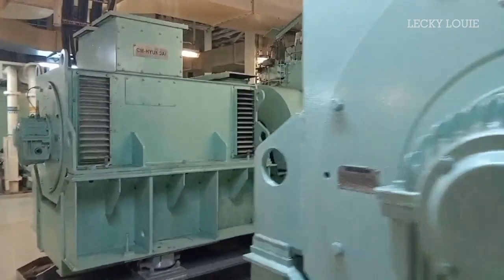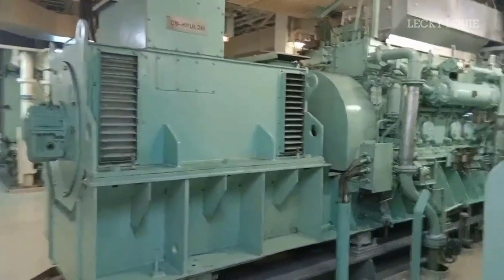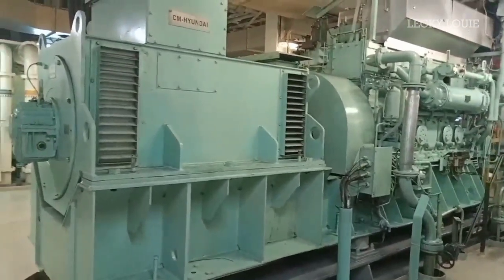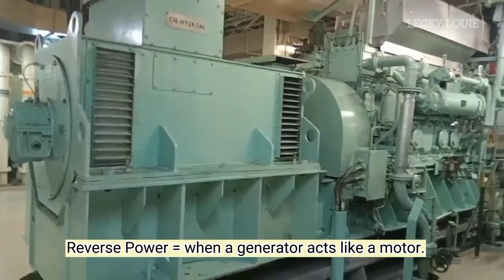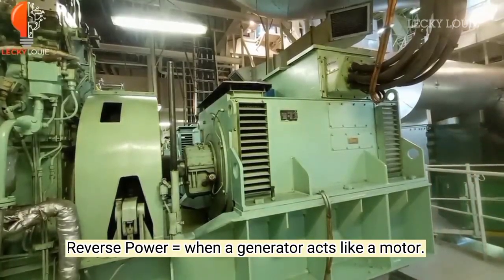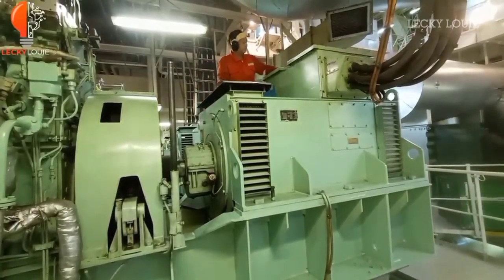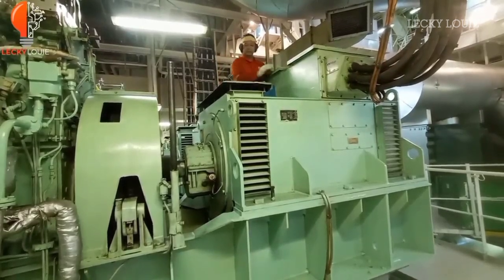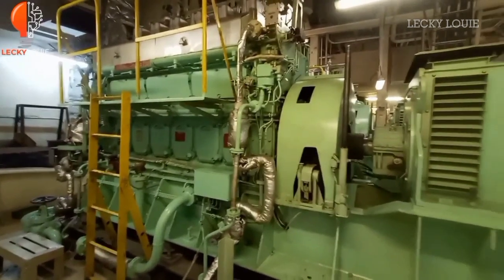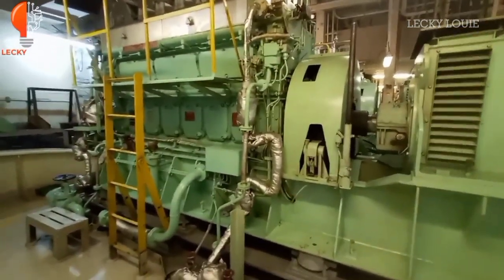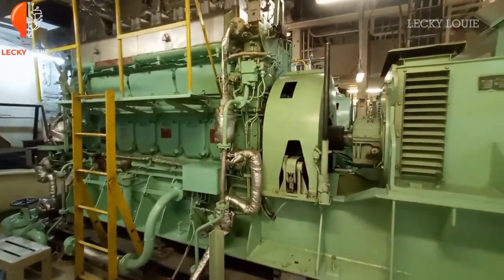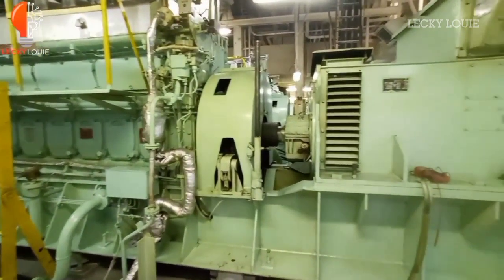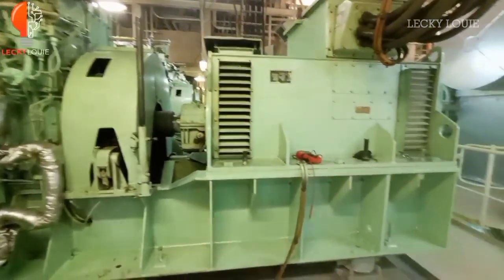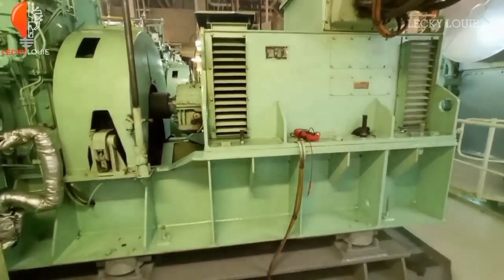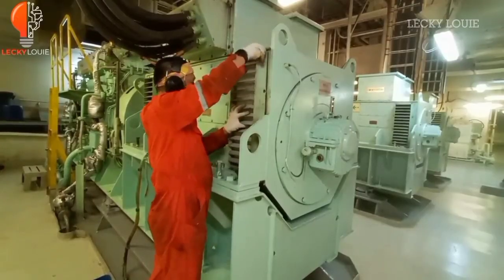Reverse power is the condition when the alternator draws power from the bus bar, which results in the alternator acting like a motor which is keeping the generator and its prime mover spinning at a particular speed. On board, the prime mover of our generator is the diesel engine, or commonly called auxiliary engine. When reverse power happens, the generator acts like a motor, it could damage the auxiliary engine, and at the same time, the generator in service could become overloaded.